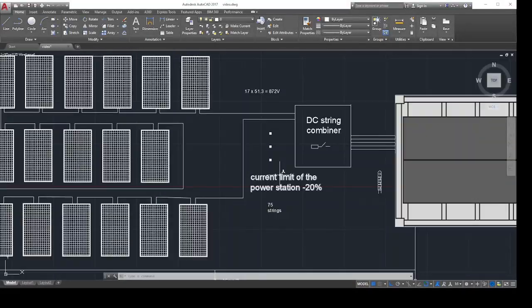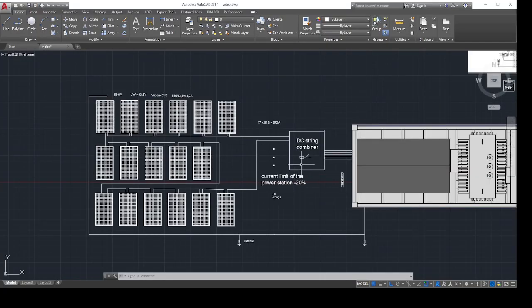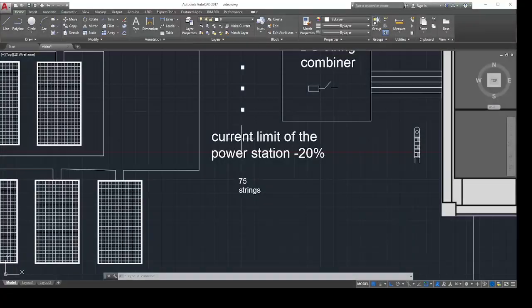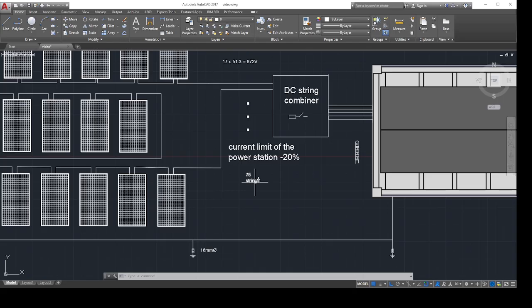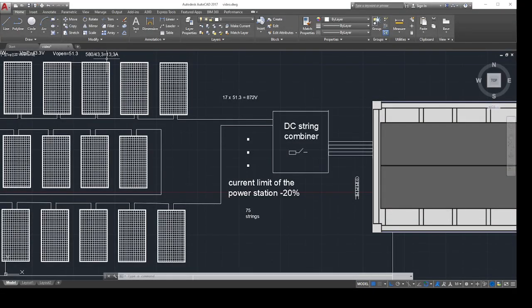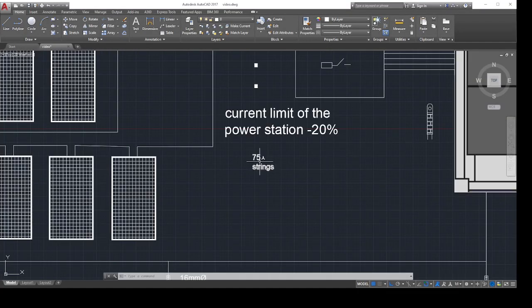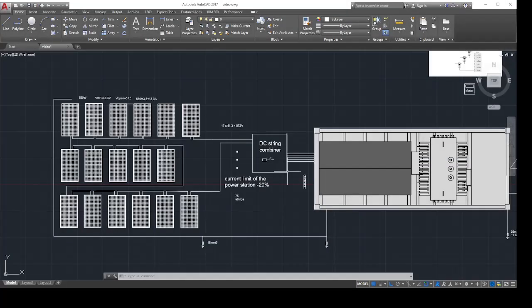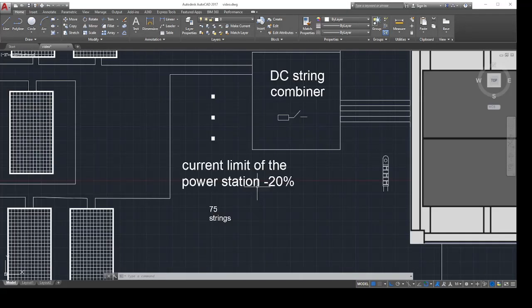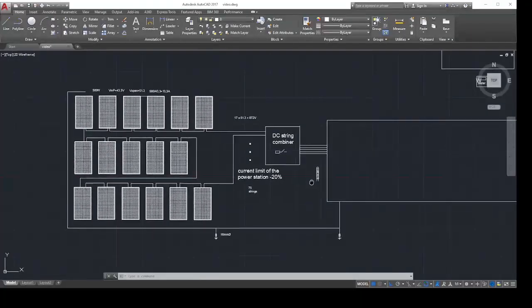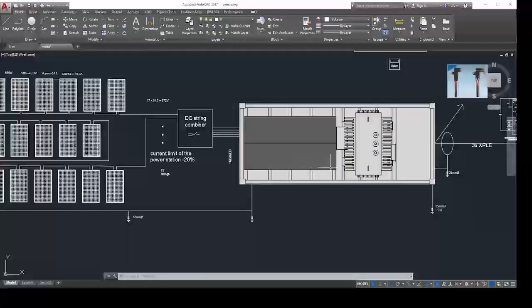So you can connect the strings with the string combiner that we already saw before - in this case, 75 strings. You can connect this because it's a 13.3 amp string, 872 volts, and you can connect. We need, like I said before, five string combiners connected together to connect 75 strings, for a total of 1125 amps minus 20%. So I calculated everything minus 20% because we never know.